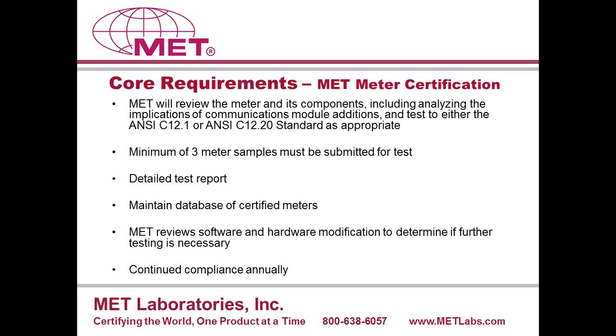Beyond that, there's an annual continuing compliance program where, if nothing's changed with the product, at the very least we would bring it in just for a quick accuracy check and keep the check and balance going, to make sure that the product does continue to comply with the accuracy portion of the standard for full load, light load, power factor testing. So, a baseline minimum accuracy check.